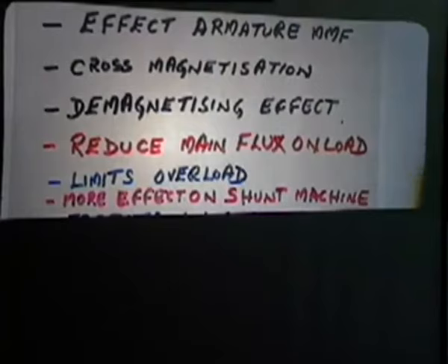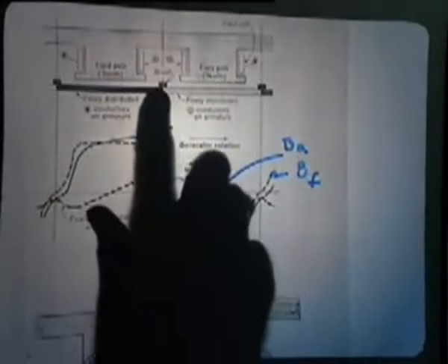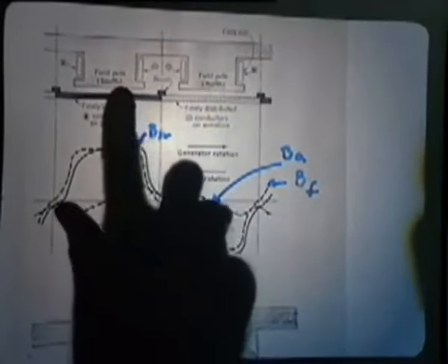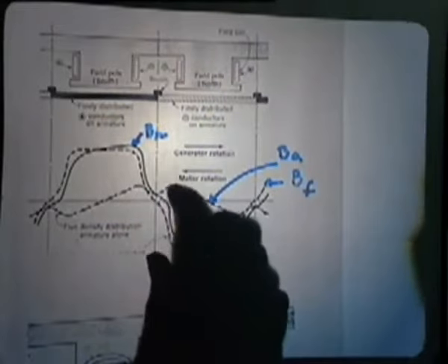The immediate problem, as we say, is there is a distortion, and we would like to reduce the distortion in the flux density patterns. One way to do it is to make the reluctance in the interpolar region higher. If we go back to this slide, if we can somehow make this reluctance higher in the interpolar region, we can reduce this cross magnetizing effect. So it means flux density due to this we should try to reduce here. Okay. So that is often done.